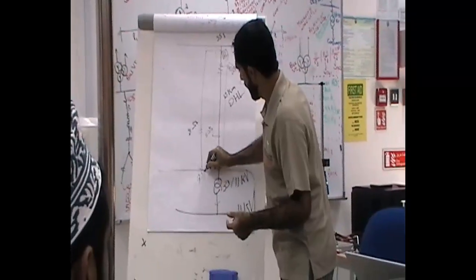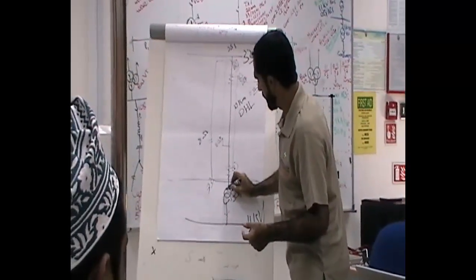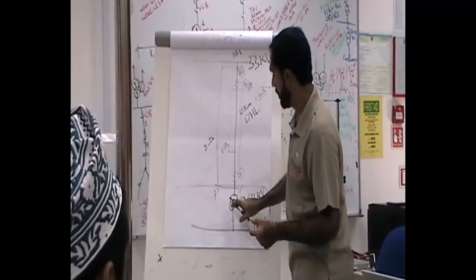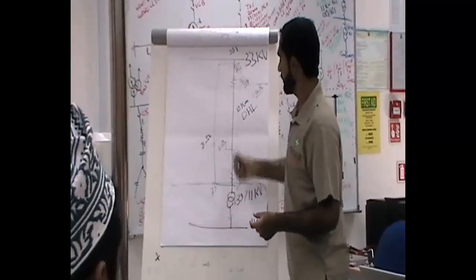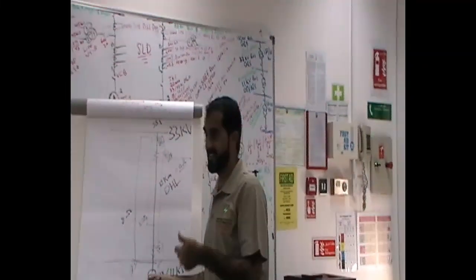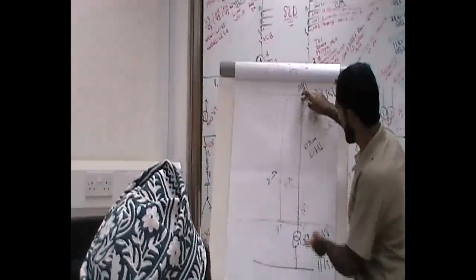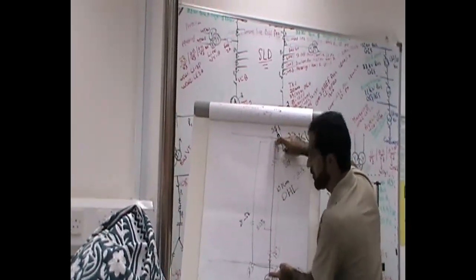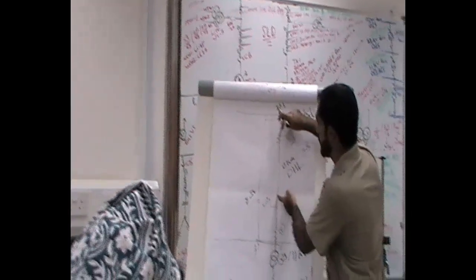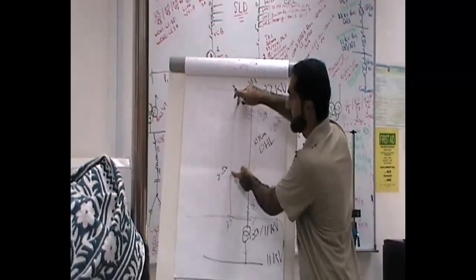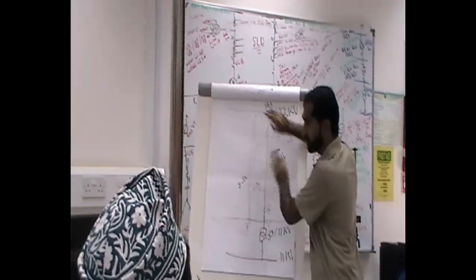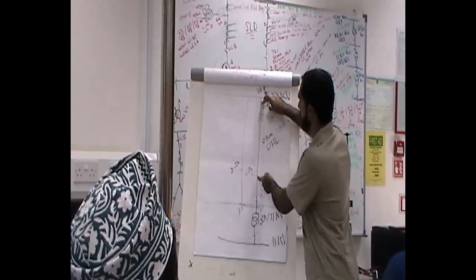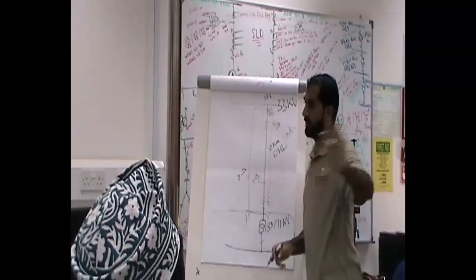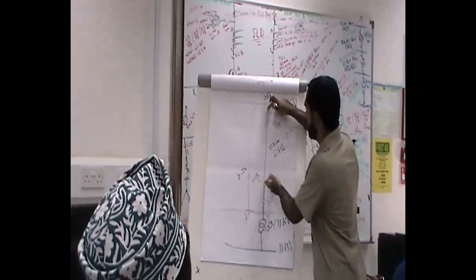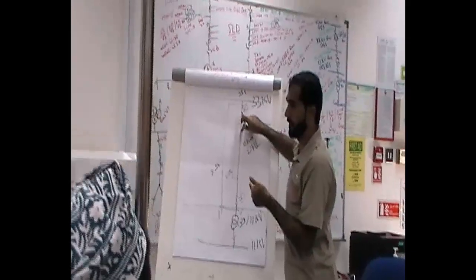Now I have zone 2. I'll extend it a little bit to reach at least, let's say, the 33 kV side of this substation, or at least half the transformer impedance. After 120%. Exactly, 120% of the line. When I'm saying 100% of the line, it's this. If I extend it 20%, it goes up to here a little bit. Now, if the fault is here, which zone will trip? If 1 didn't trip, 2 will trip. But basically, it's not backup for zone 1. If zone 1 didn't operate, definitely zone 2 will not operate, means the relay is faulty or some issue with it. But if the fault is here, the fast zone will be zone 1. It will trip. That's why I selected one point in zone 1 and I've checked the tripping.